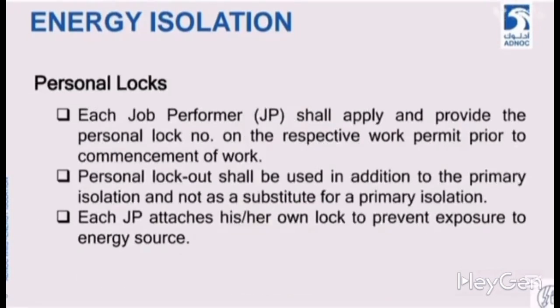Personal lock. Each job performer shall apply and provide the personal lock number on the respective work permit prior to the commencement of work. After the zero energy demonstration, every JP will apply their lock where the PI's lock is, where the ISO has placed a lock, and where the area operator has placed their lock. The JP's lock number should be noted down. It should be attached to the certificate with their permit. Only then can you start the work.